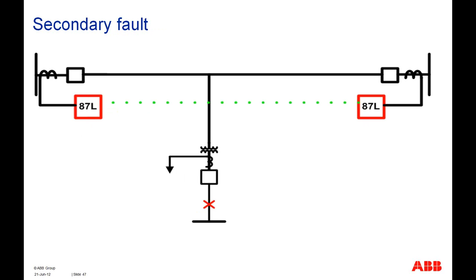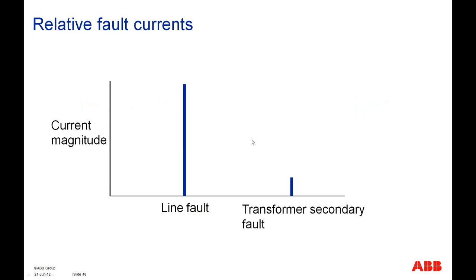The criterion which is used to detect faults in the tapped line on the secondary side of the transformer is that the fault level on the secondary side of the transformer is quite low as compared to the fault level on the transmission line. So, which is shown over here: that's your line fault current, and this is your transformer secondary fault current, which is quite less. So we use this criterion to get the protection of the tapped lines without even measuring the tapped line current.